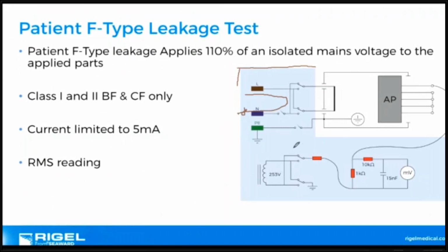What we're doing is we're putting this voltage on, so any current would flow to the applied part. So we're putting on that 110%, so if you have 230 volts, that would be 254 volts, there and thereabouts. Apologies for the rubbish drawing.